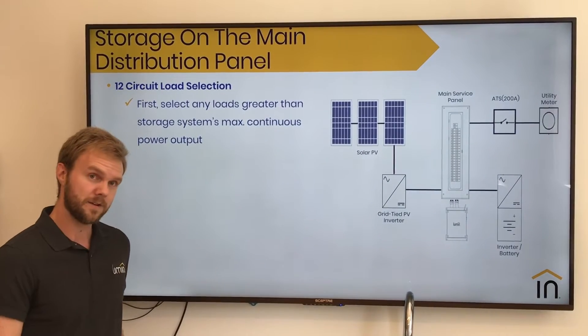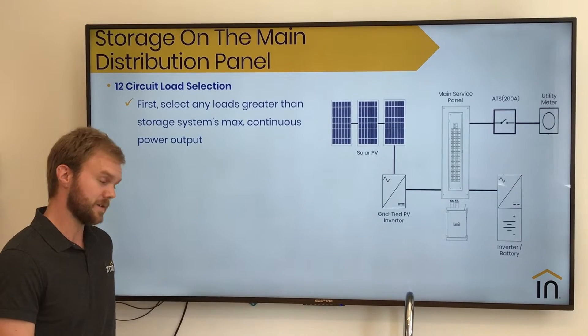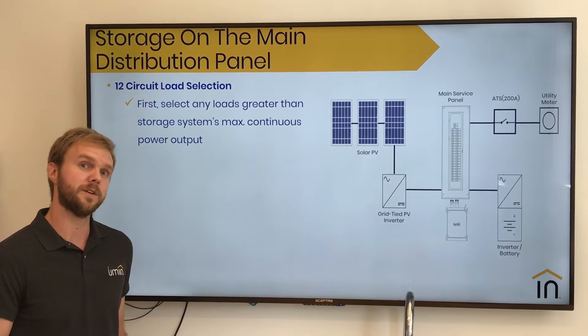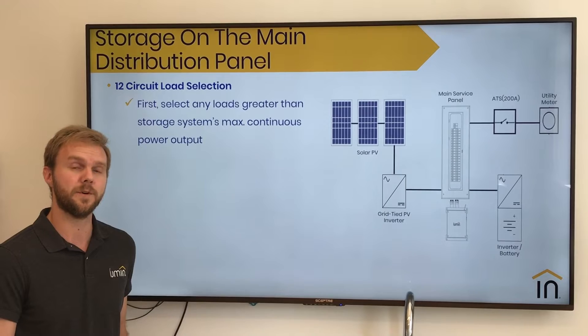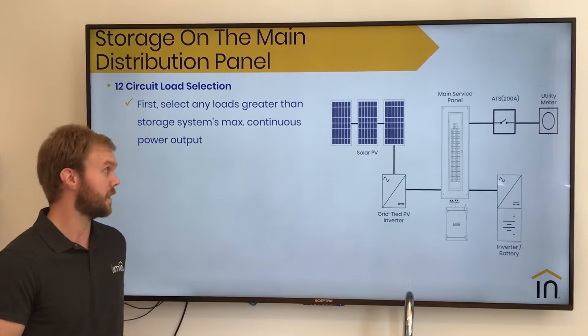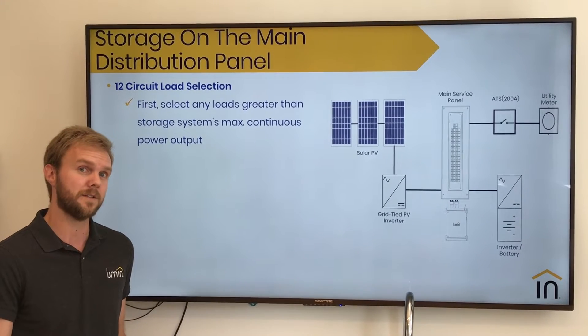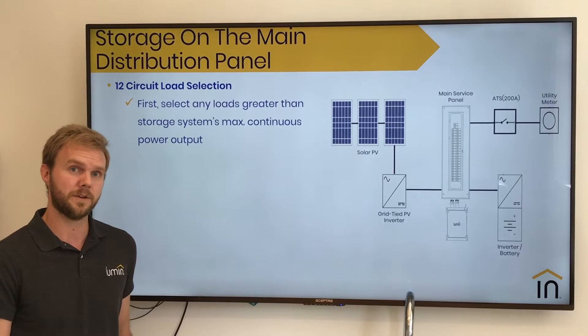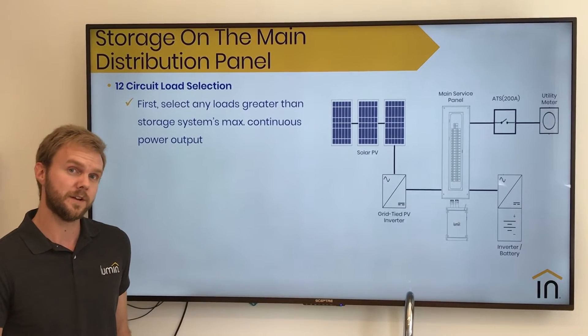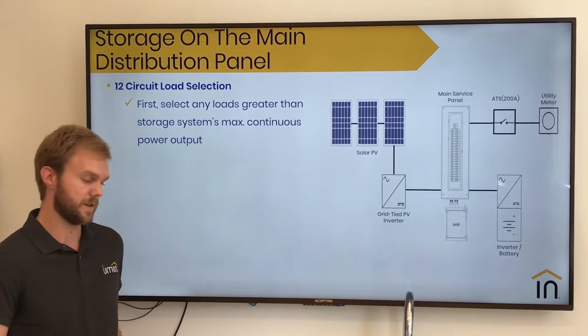When you're installing your Lumin and your storage system on a main distribution panel, the first thing we recommend is selecting any loads that are greater than what your storage system is rated for. So if you have a battery system that's rated for 30 amps, we first recommend looking at that main distribution panel and seeing which circuits are rated higher than 30 amps and connecting those to your Lumin smart panel first. The intention here is to immediately shed those loads during an outage to better protect your battery system.